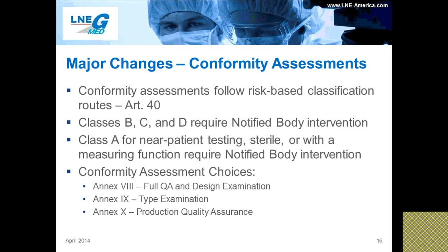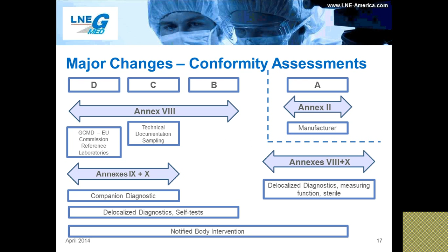Now on this slide, you'll see a chart that details the conformity assessment and which classes can use which assessment. As you can see, full quality assurance, or Annex 8, is available for classes D, C, and B. Along with Annex 8, Class C devices also require a technical documentation sampling, where Class D devices have to send some of their samples or batches to the EU Reference Laboratory. Also note that Annex 8 states that the manufacturer should grant the notified body access to the technical documentation, regardless of the class. The conformity assessments in Annexes 9 and 10 are available for classes D and C. Notified bodies are required for all classes of IVDs, except those in Class A that aren't sterile, have a measuring function, or offer near-patient testing.